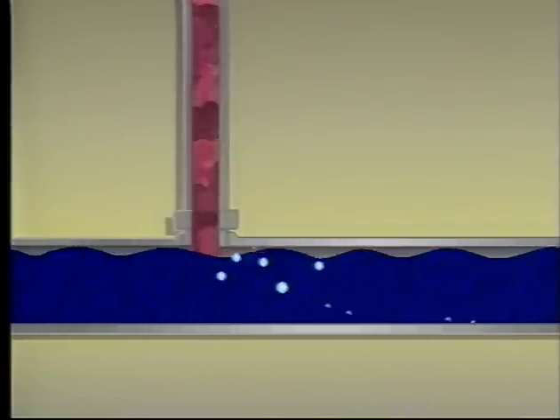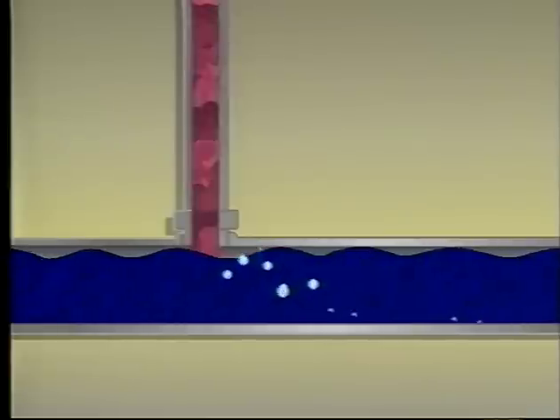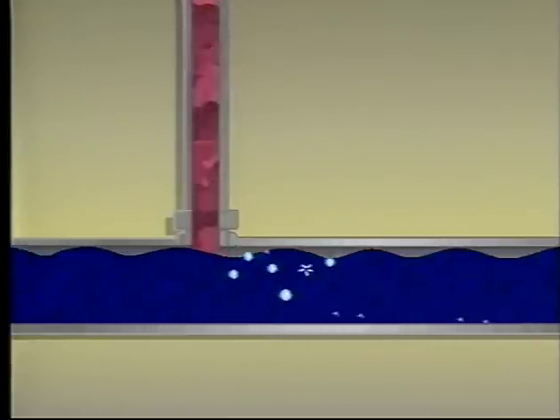The flash steam immediately collapses again when it encounters the relatively cool pump discharge water. This thermal shock often causes damaging water hammer.